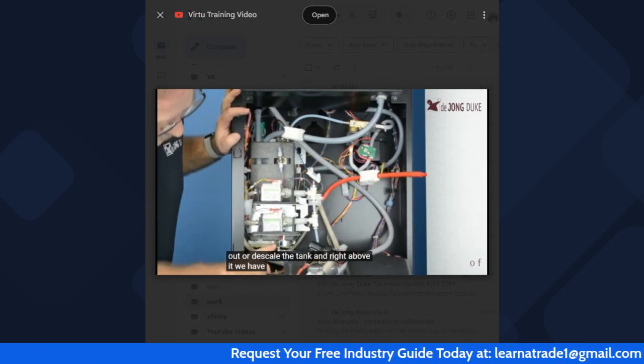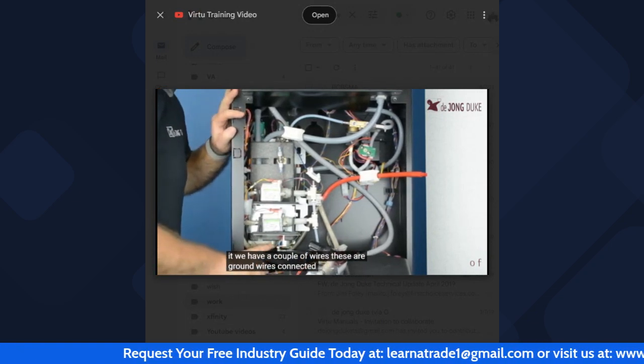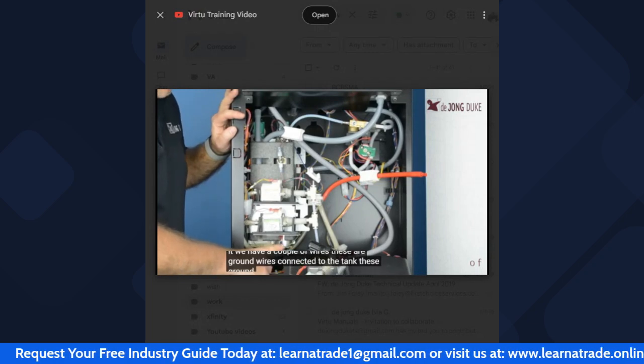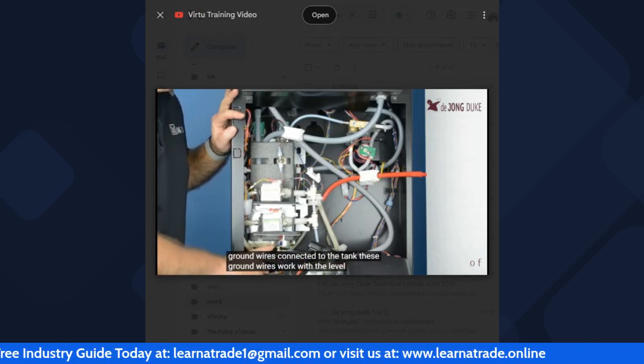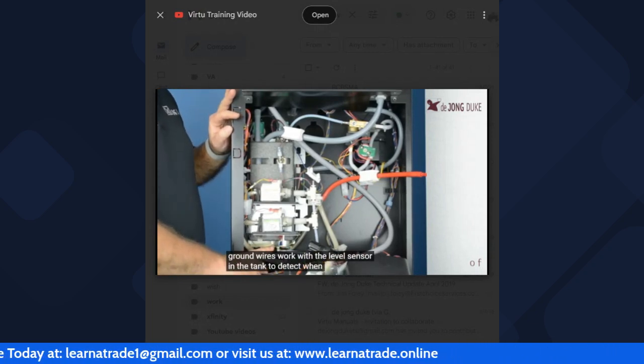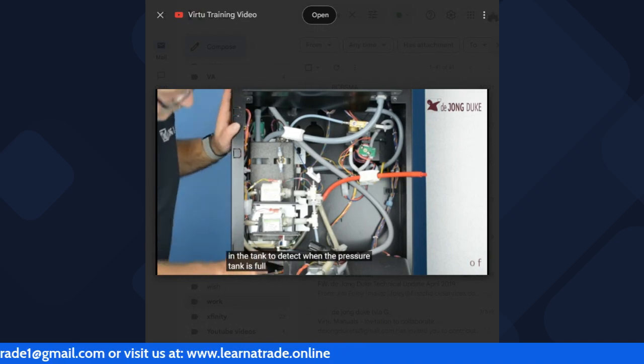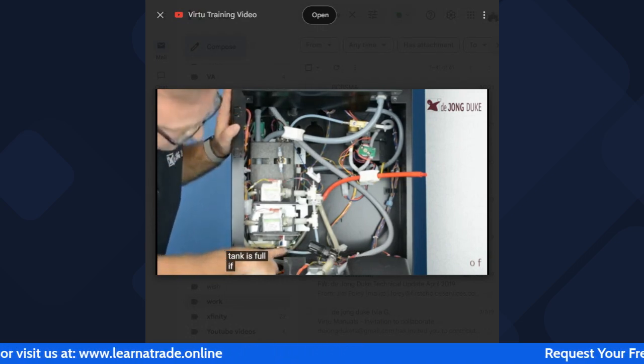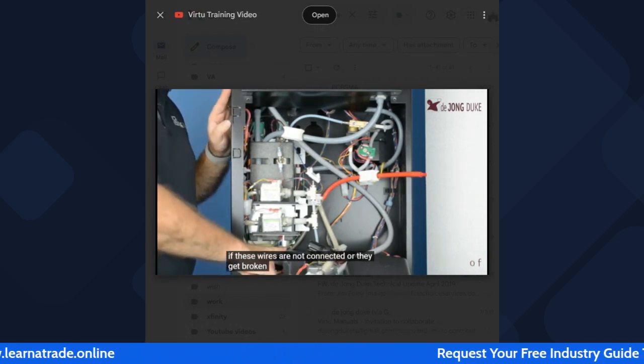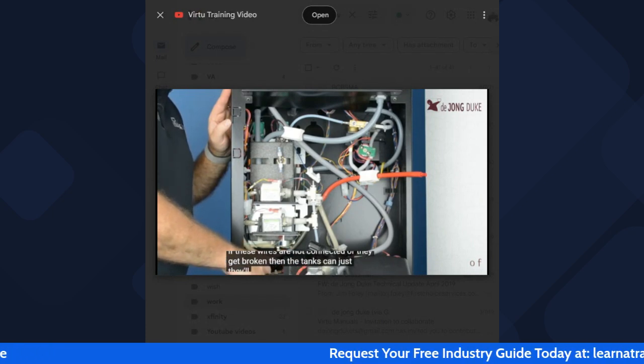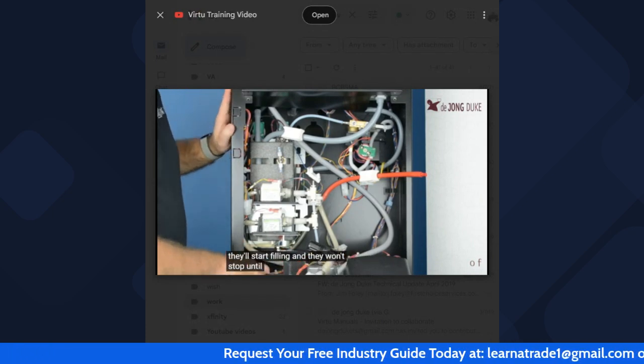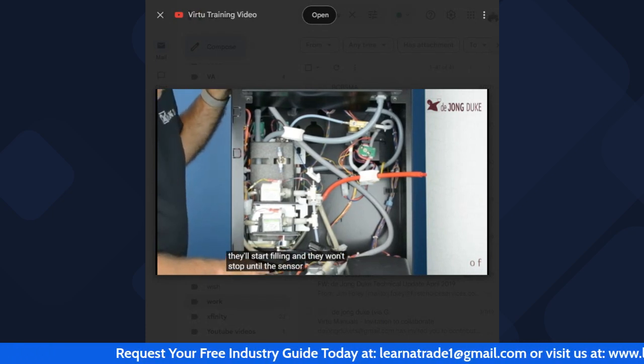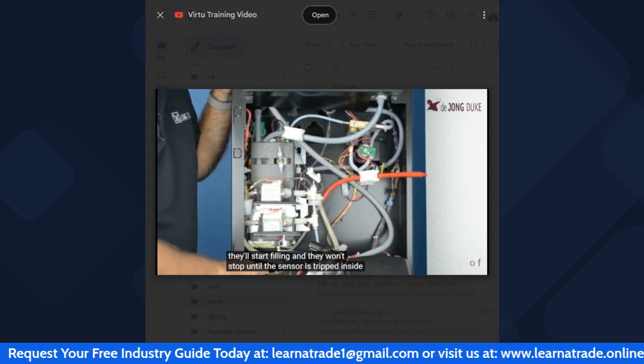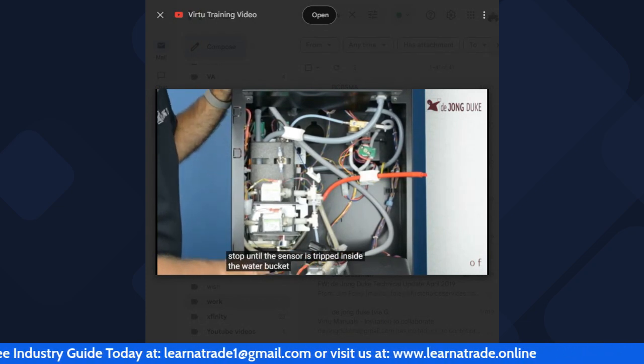And right above it, we have a couple of wires. These are ground wires connected to the tank. These ground wires work with the level sensor in the tank to detect when the pressure tank is full. If these wires are not connected or they get broken, then the tank will start filling and won't stop until the sensor is tripped inside the water bucket.